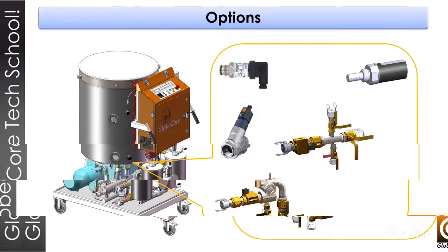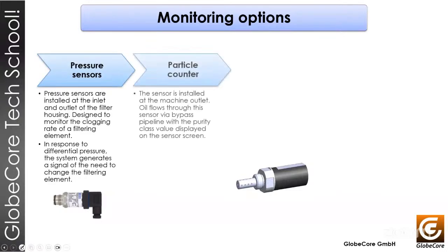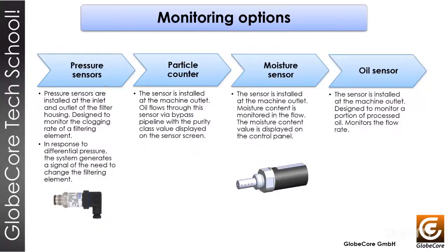Some different parts that we can add to the machine are the pressure sensors. This sensor will indicate to you if you have to replace the filter elements. We can add a particle counter that will help you to know the quality of the oil inside of the machine. That will help you to know if you have a lot of solid contamination. Another important one is the moisture sensor. You can know the level of moisture inside of your oil, because you can have inlet and outlet moisture sensors.